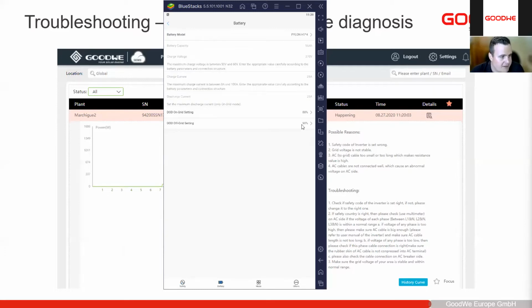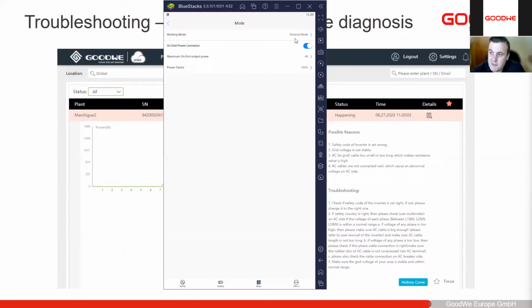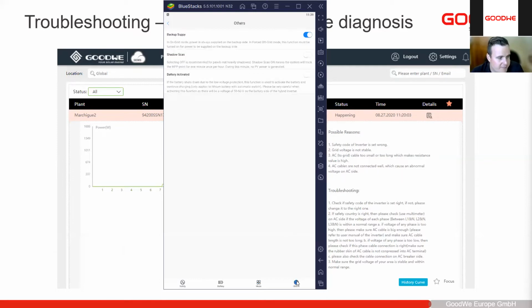Even under the battery side, you can change the on-grid and off-grid depth of discharges on the devices. You can see, so if there's a battery problem, you can come and see and make sure the correct batteries are selected. The operating work mode, which the device is set in, is in general mode, is it backup mode, is it economic mode, as well as the export power limit as well that one could set. And then a few advanced functions that one can enable or disable.